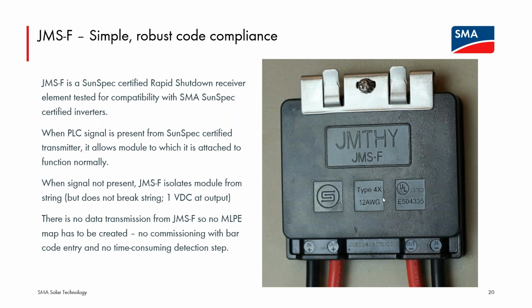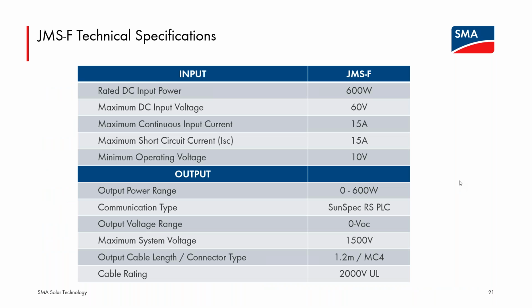The JMSF device, if you haven't seen it, is a very simple device meant to add on to a PV module, connect to the PV module junction box leads, and then build your code compliant string with the output leads. So attaching this to the module gives you that rapid shutdown compliant module, and then you build the system as before and turn on the transmitter in the CORE1. The JMSF device handles modules up to 600 watts, up to 60 volts and 15 amps. So there is not a residential versus a commercial version of this device. If it works with the module, you can use it with either of our inverter lines that have that SunSpec transmitter built into it.